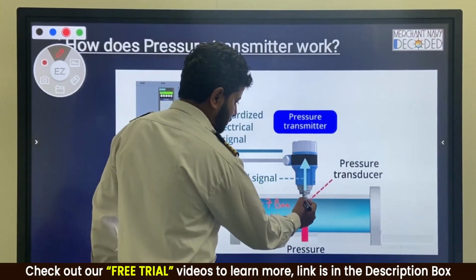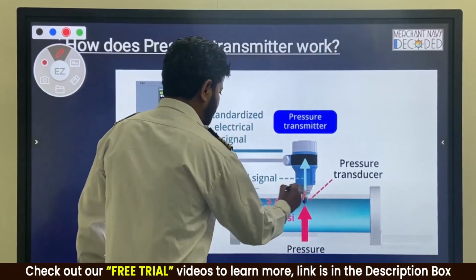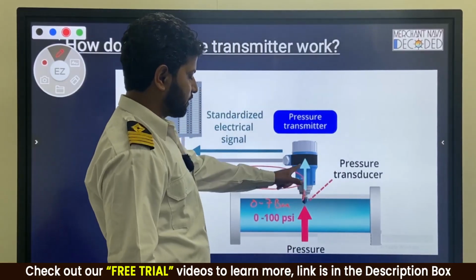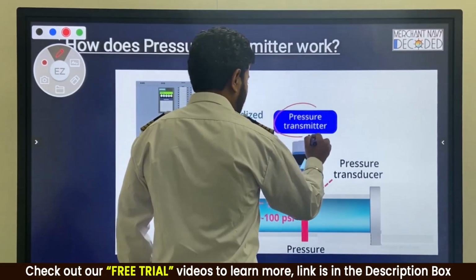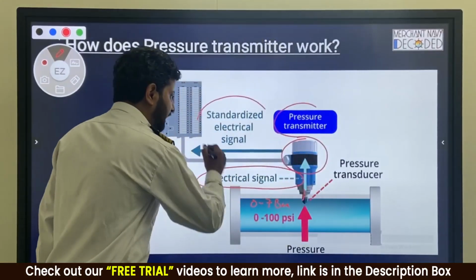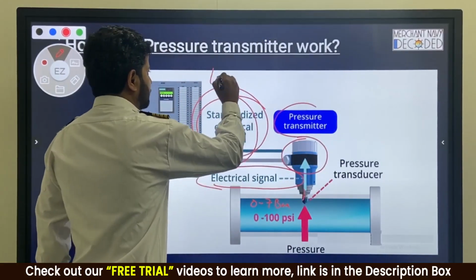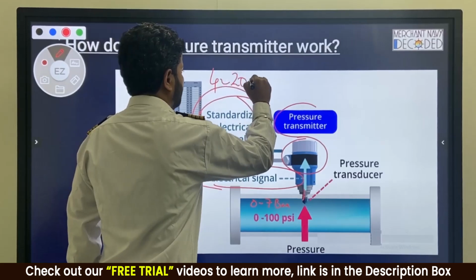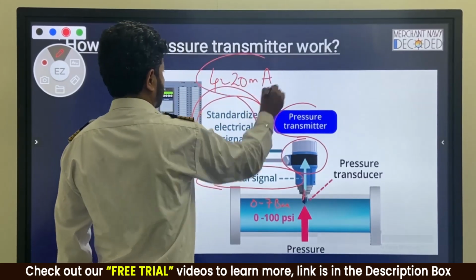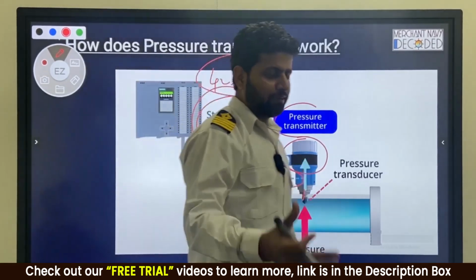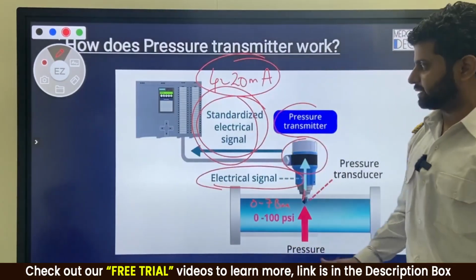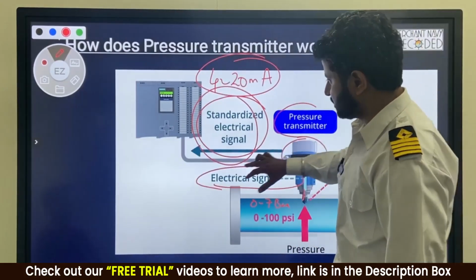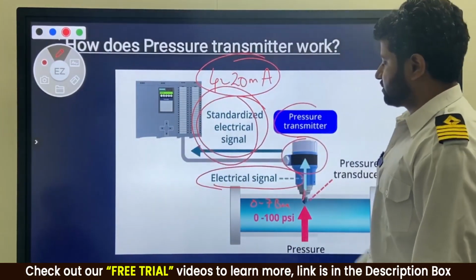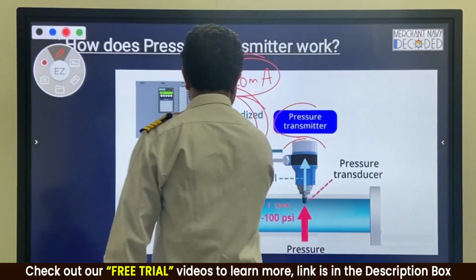So this is a pressure transducer fitted and an electrical signal is generated. So this pressure is converted to an electrical signal. Then this pressure transmitter body converts it into a standardized electrical signal, that is 4 to 20 milliamps. When I was discussing the temperature transmitter, you understood very well what I mean by 4 to 20 milliamps and why it is needed. But here the same pressure transmitter is also doing the same thing. So this is a 4 to 20 milliamp signal coming.